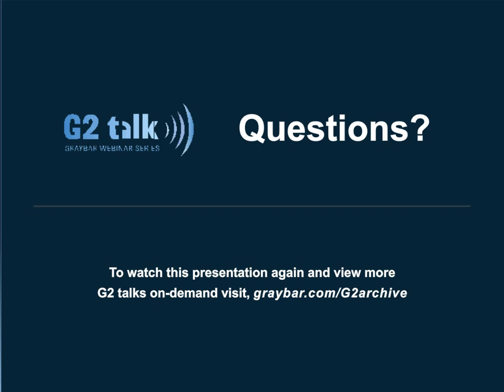All right, thank you. Dan, if we do an arc flash hazard analysis, are we OSHA compliant and don't need to do anything else? That is a great question, and something I always hear. The answer, unfortunately, is no. Doing the arc flash hazard analysis is always the first step to working safely. However, I look at it like a marriage. Getting married is not the end of the road, it's the start of it. Besides just doing an arc flash hazard analysis, you need to develop an effective electrical safety program and document safe work practices. So there is a ton more than just doing an arc flash study to be compliant with OSHA.